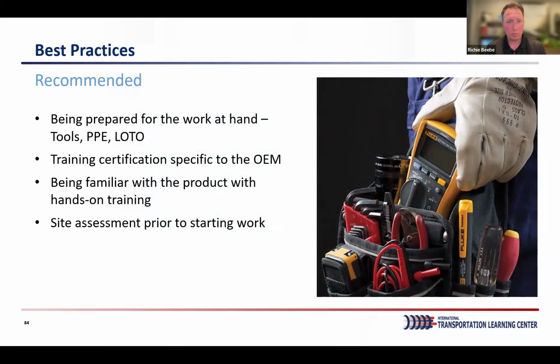Best practice for working on a piece of EV equipment is being prepared for the work at hand - understanding what the OEM requires, having the proper tools, the PPE, the lockout tagout equipment, and assessing what the issue is when we show up to a site. It could be anywhere from a power outage to corrective maintenance. Really understanding what needs to be done and having all the tools, equipment, and knowledge sets our technicians up for success to repair the unit, get it back online, and prevent any return trips to that site. First-time fixes is what we're going for.